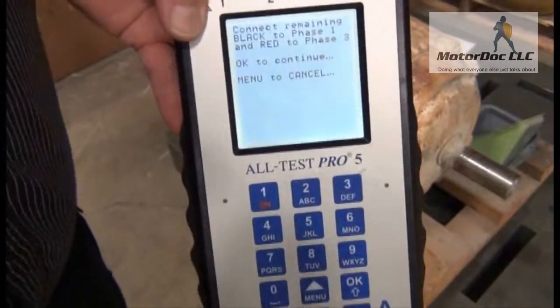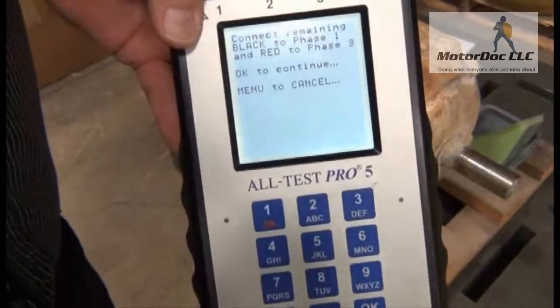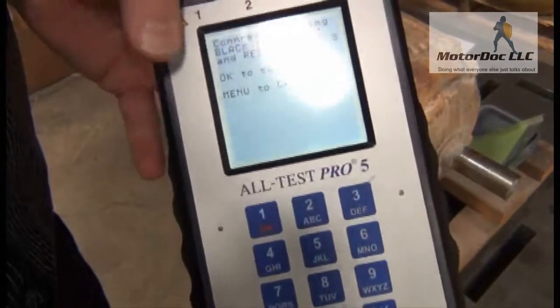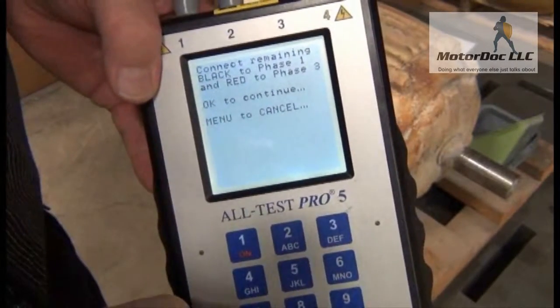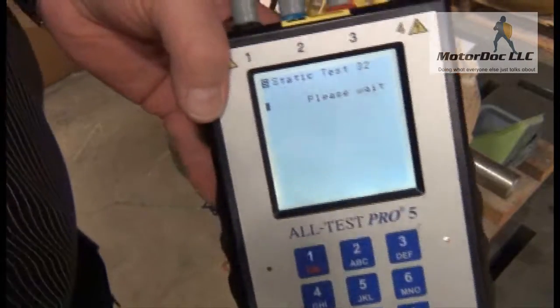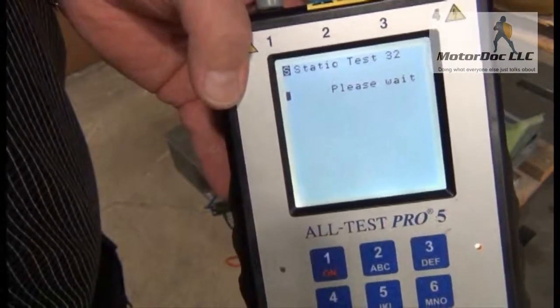Now this will test more than a thousand feet from the motor. When you do that, it's usually not recommended to do the dissipation factor capacitance test, unless you want to see the entire circuit. So once I'm here, I press OK. And it's going to go ahead and do the other test. I just have to wait.